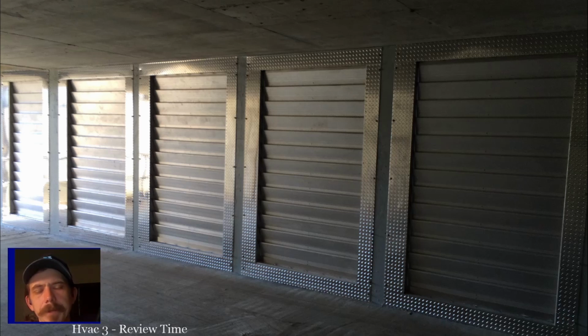I would say, well, I don't have any personal experience, so I can't say. In general, I start to get a little bit scared if you get below 1 million, and I start to really get scared when you get below 500,000 ohms. You get below 500,000 ohms, and I'm going to start questioning whether or not this motor is okay. But the technically correct value is that you should see no less than 100,000 ohms to ground on an ECM. So keep that in mind.